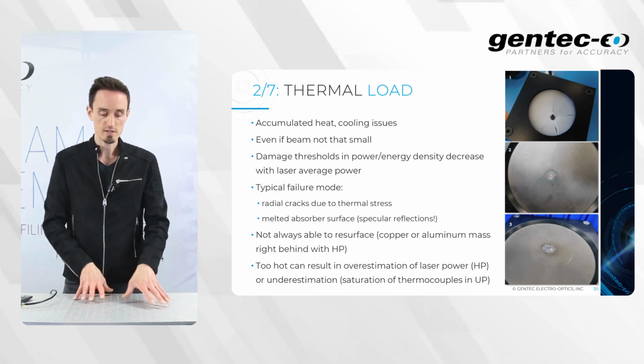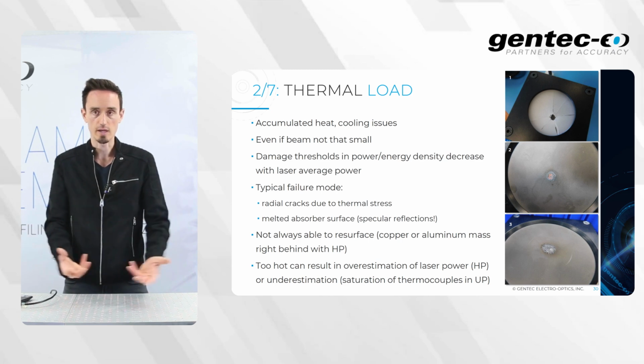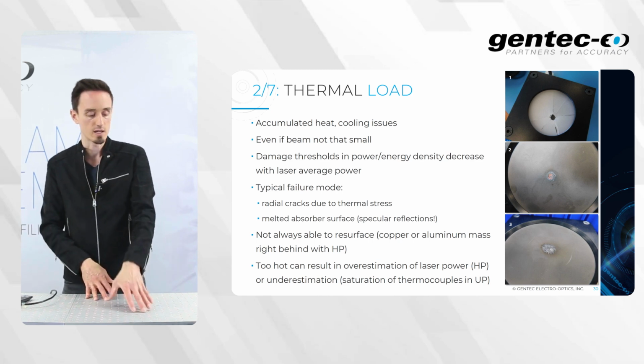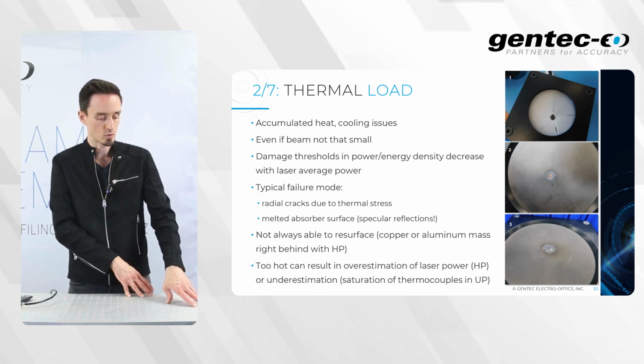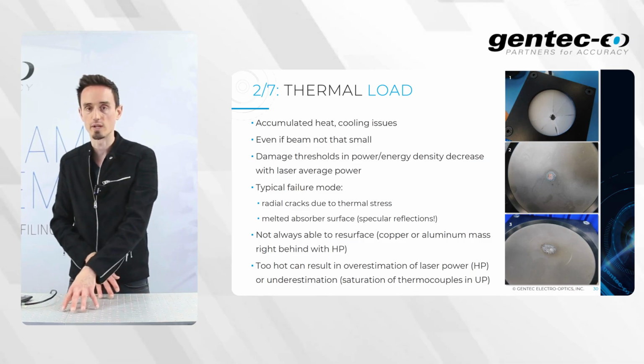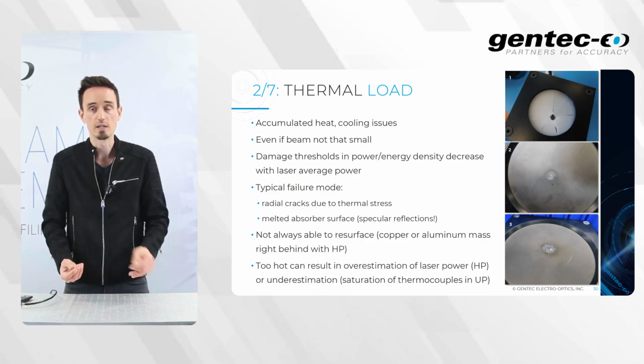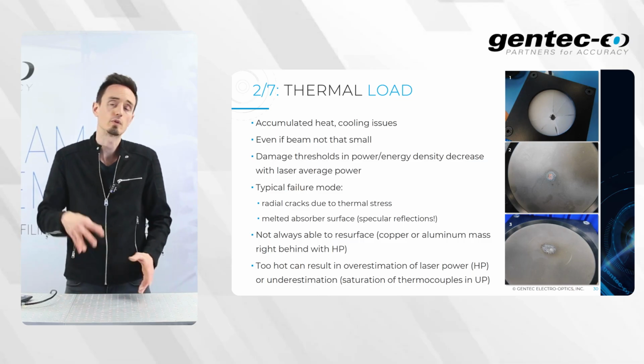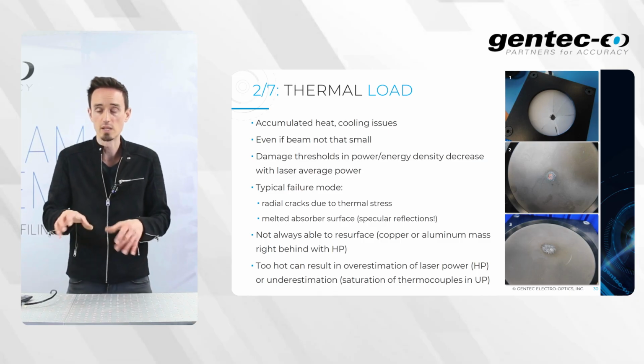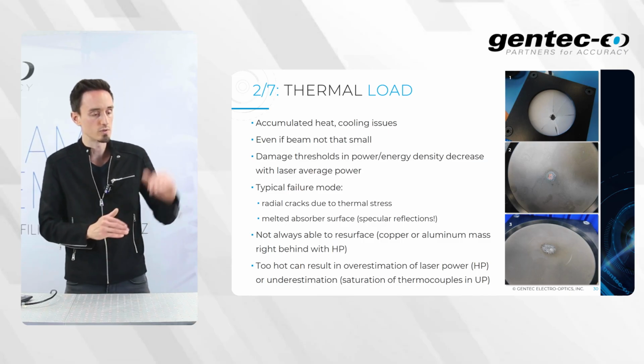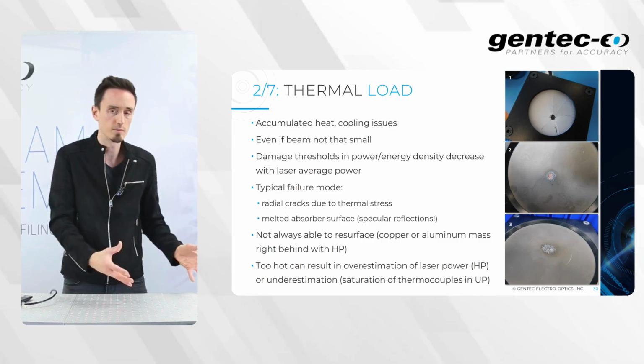When using the water-based calorimeter, if it gets too hot around, because it is relying, again, on two things, temperature measurement, water temperature measurement, and water flow rate measurement, if you have a too hot environment, that will result in an overestimation of the laser power with those HP water-based calorimeters. The measurement will appear too high because of a too hot environment.